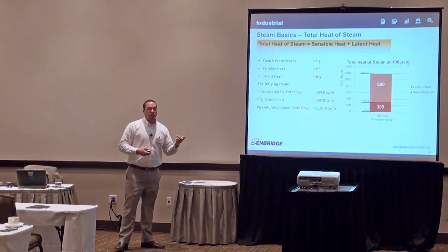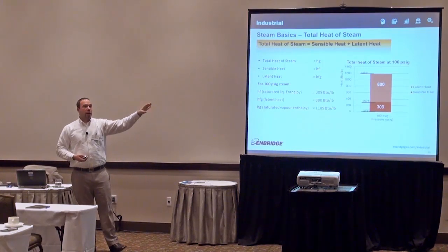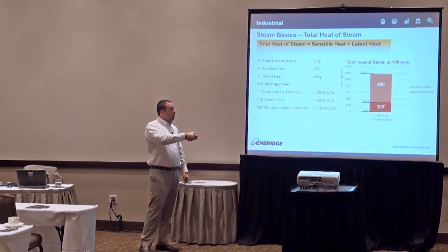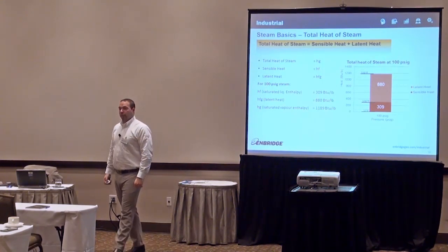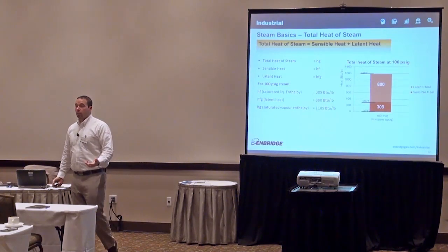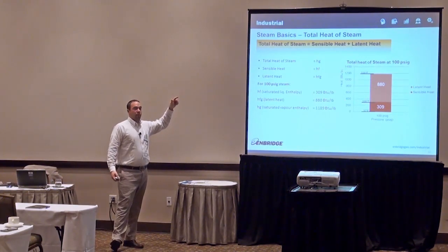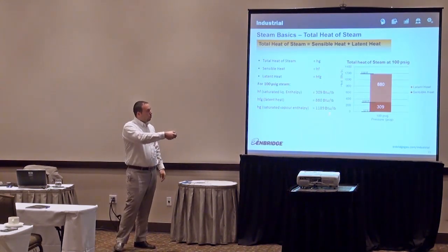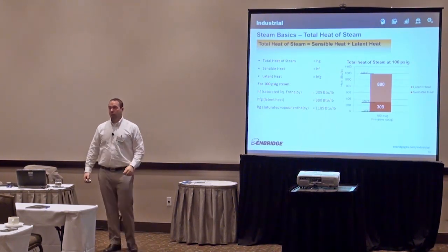HG is the sum of the two. So if you were to throw that pound of steam in the garbage, how many BTUs did you just throw out? You've thrown out both the latent part, which we want, as well as the sensible. So if you have things like failed steam traps and the vent on your condenser or your condensate receiver is just venting steam, you're throwing out both the sensible portion plus the latent portion.